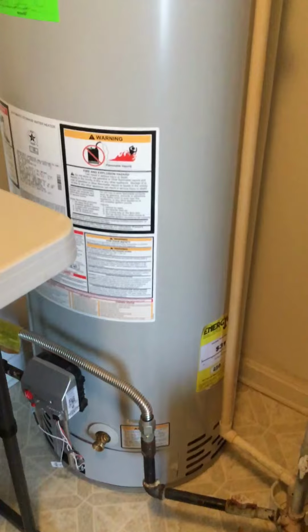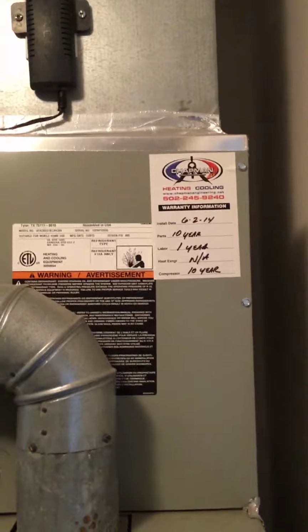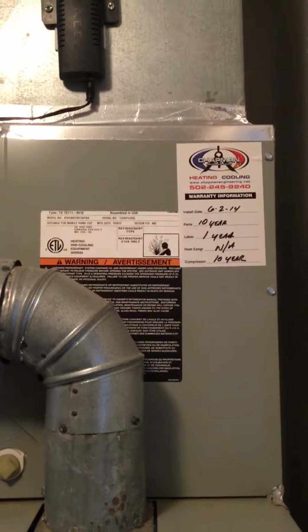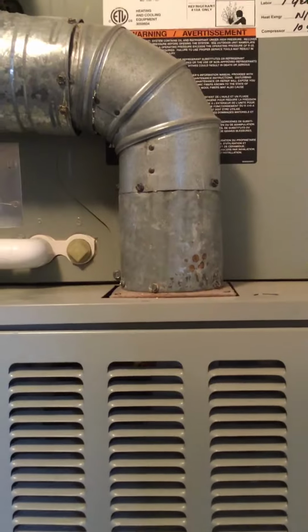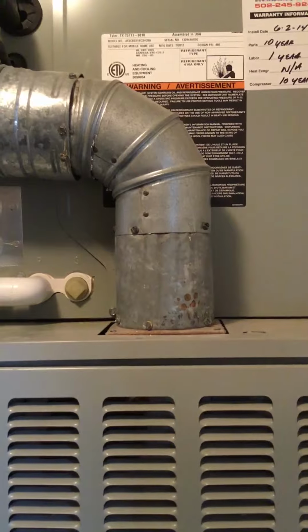We've had the plumbing company come out. They've checked the air conditioning ductwork all the way to the roof. It is clear. The burners they took out and looked at because everything was still under warranty, and they say everything's working perfectly. We had the HVAC people come out. They said the problem is the water heater and it's not the air conditioning. The plumbing company ran smoke tests that proved that the water heater backdrafted only when the air conditioner was running.